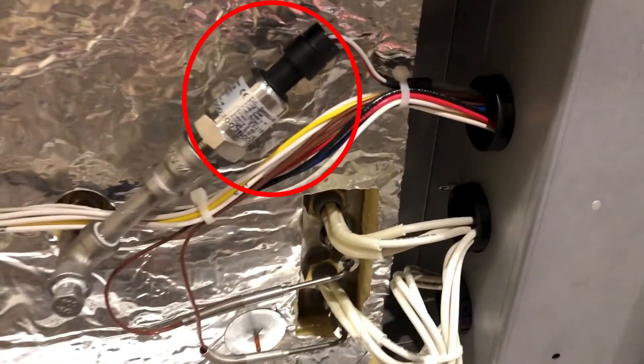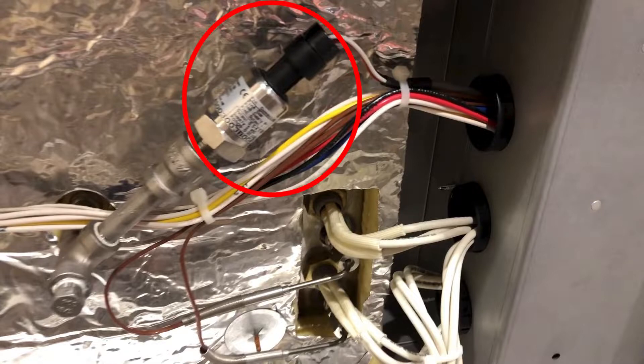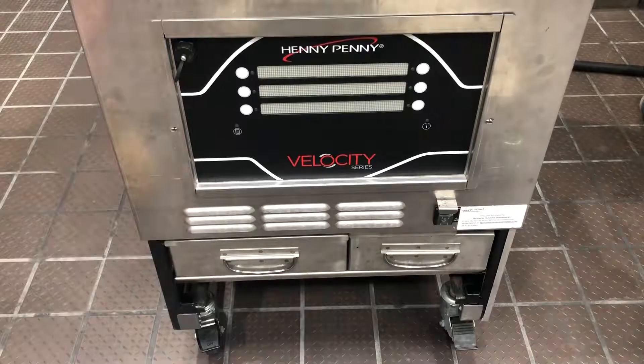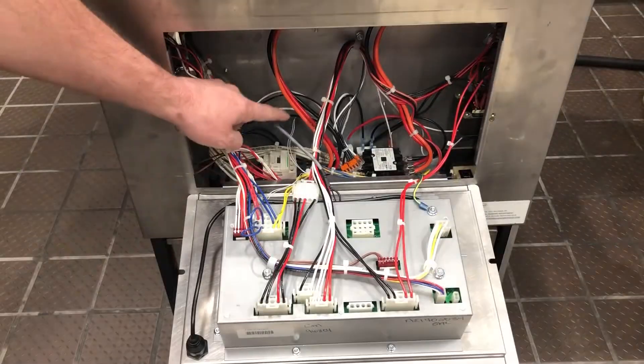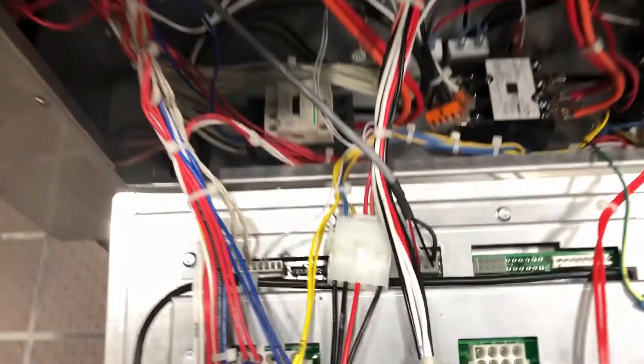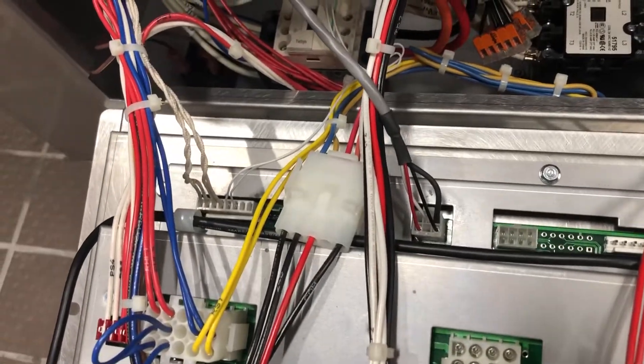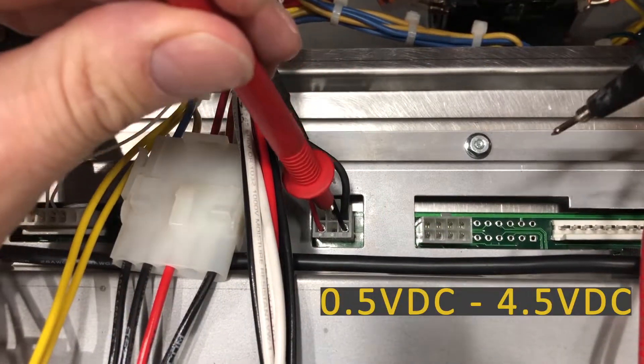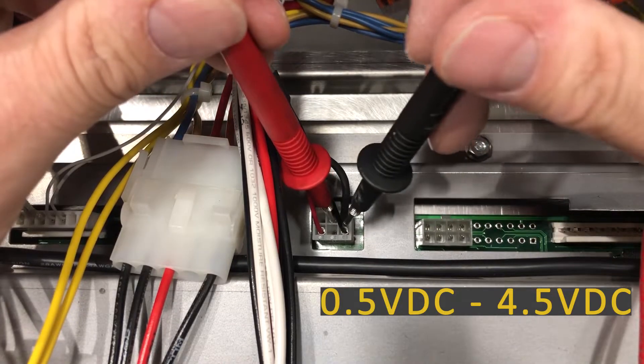The pressure transducer under normal operation has 5 volts DC go into it, and then it fluctuates the voltage back to the control depending on the pressure in the pot. A valid reading from the pressure transducer back to the control is between 0.5 volts DC to 4.5 volts DC.